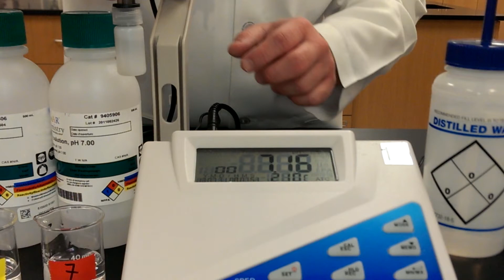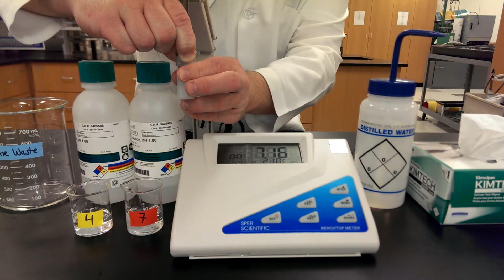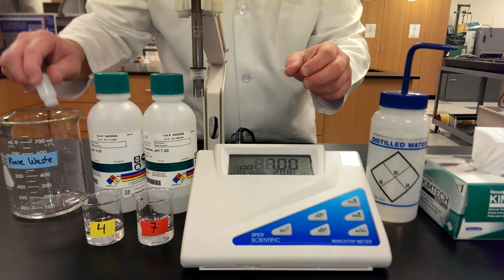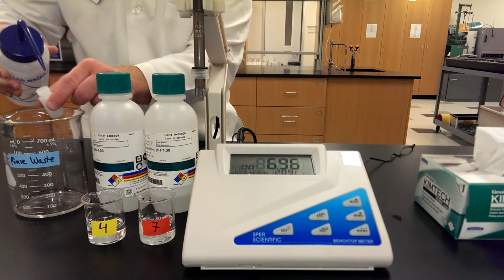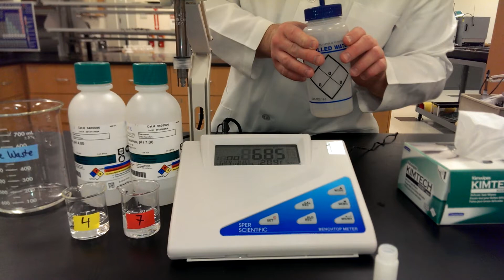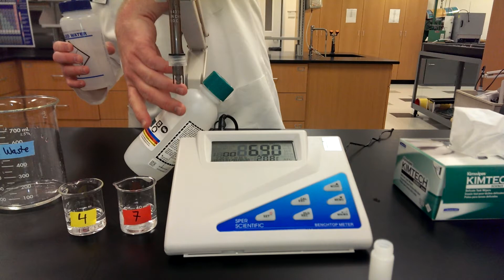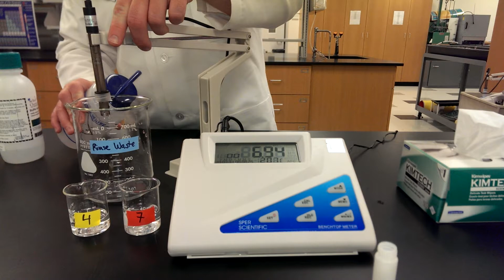First thing we're going to do is hold the top part of the cap tightly and then unscrew the bottom part. And the solution that's in there, we're going to dump that out in our waste beaker. We're going to rinse the cap out with DI water. Set that down for a second. And then we're going to rinse the probe with DI water. That way, if it's contaminated any type of way, it's going to get all that good stuff off. Alright, shake it a little bit.